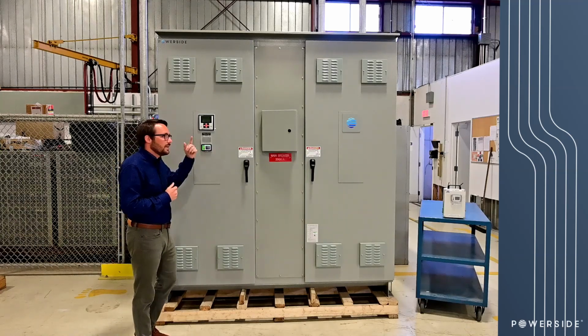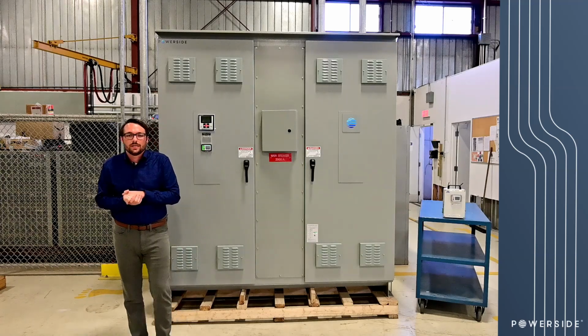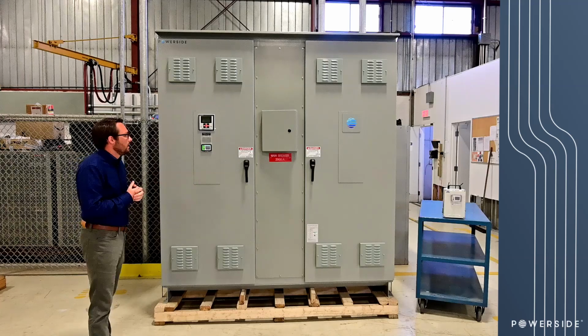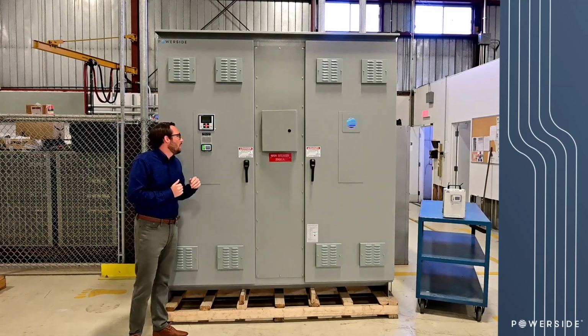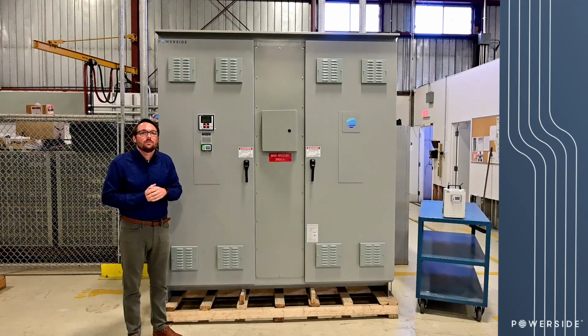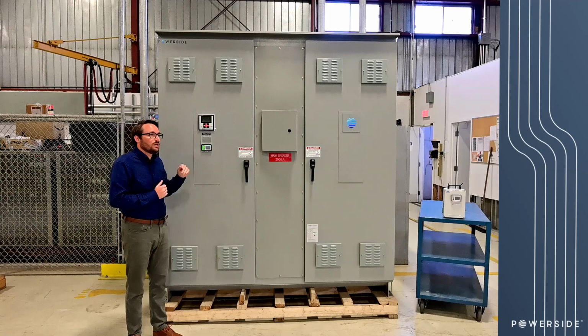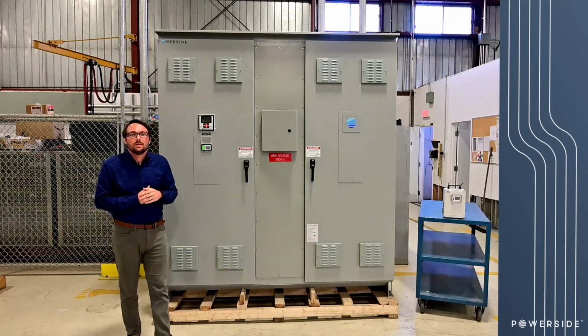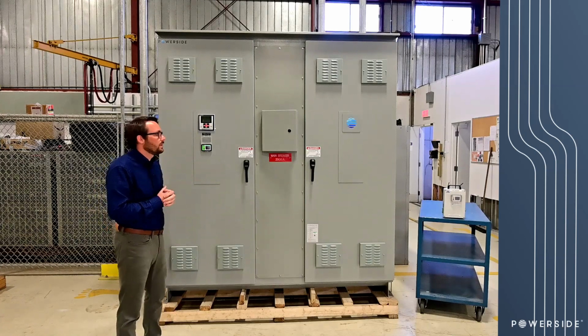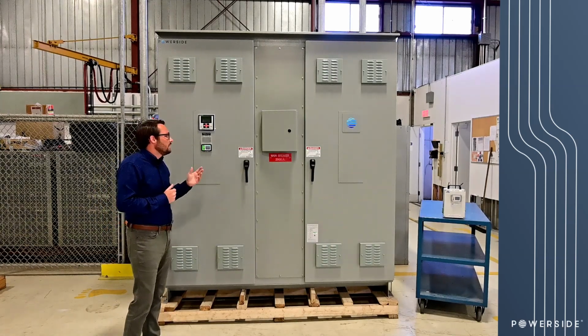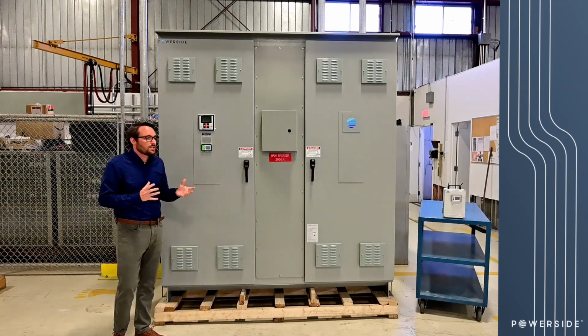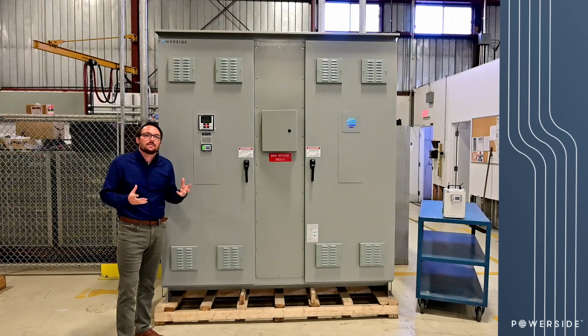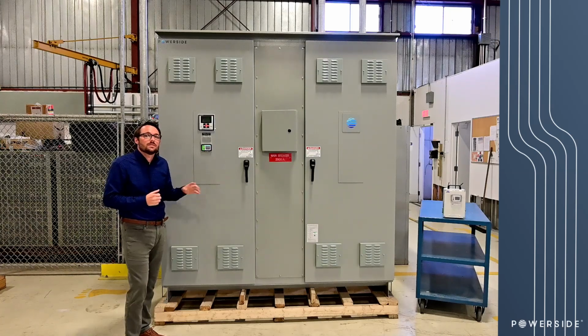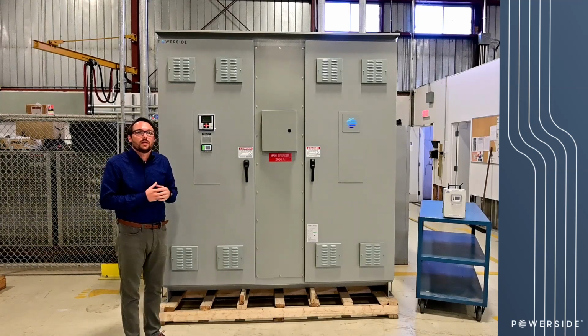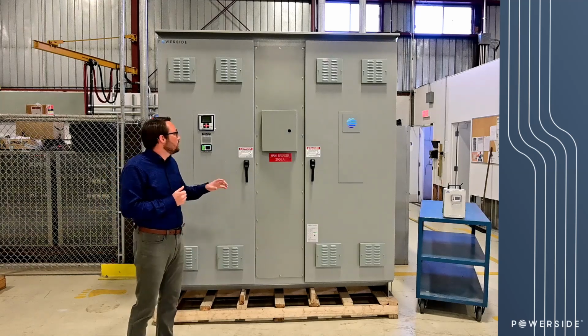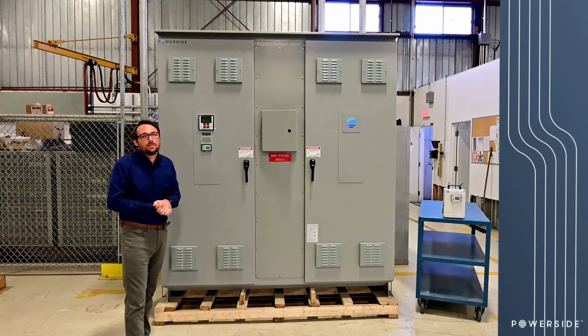And what this is going to do is send that signal up to CubeScan, which they'll be using on a regular basis to look at their power quality as well as their general load conditions. And then they'll know, hey, switchboard A, we need to go look at that capacitor bank. There was an alarm that was triggered. It may need to be serviced. There may be a blown fuse or a replacement component that needs to be looked at. And this was really valuable for this client because they don't actually have on site a robust maintenance staff that's very knowledgeable about this type of equipment. And so being able to have this set up for them, and they can get notified as soon as an alarm condition occurs, was extremely valuable.